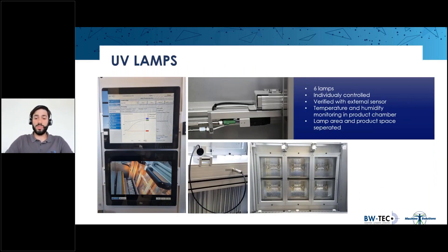You can do 21 products at a time, split into three cassettes with seven products each for ease of handling. The cassettes can be used with different holders depending on the product — for example, a magnet holder for assembly groups, or luer or push-in connectors. The coating bath uses a set of 21 tubes for base and top coat, also split in three parts. The tubes are made from stainless steel with PTFE end caps, available in 9 mm or 12 mm ID, and can be disassembled easily for cleaning. The six UV lamps are encased in a separate room to minimize heat transfer to the products. A temperature and humidity probe within the machine tracks environmental conditions during the process.